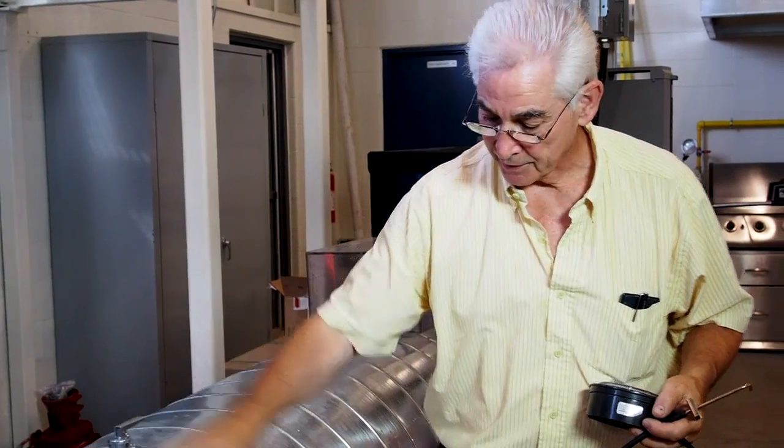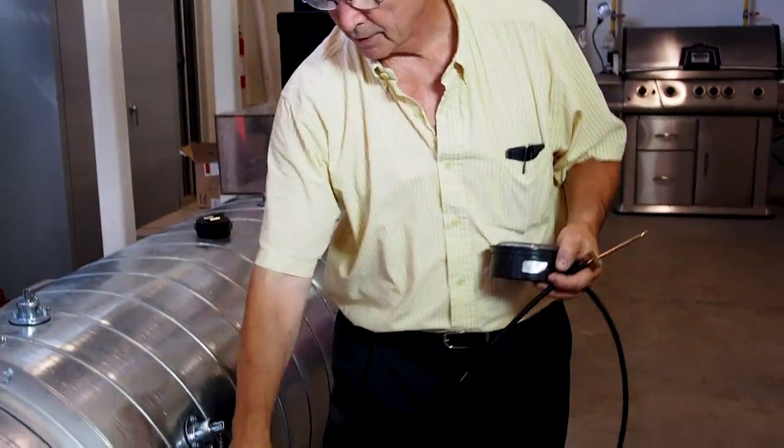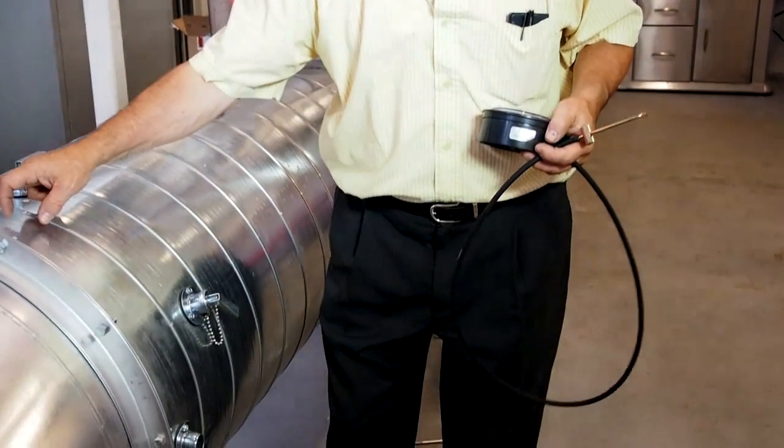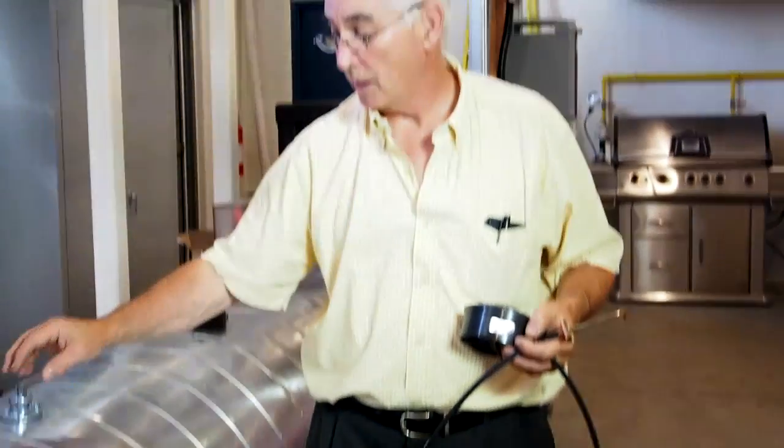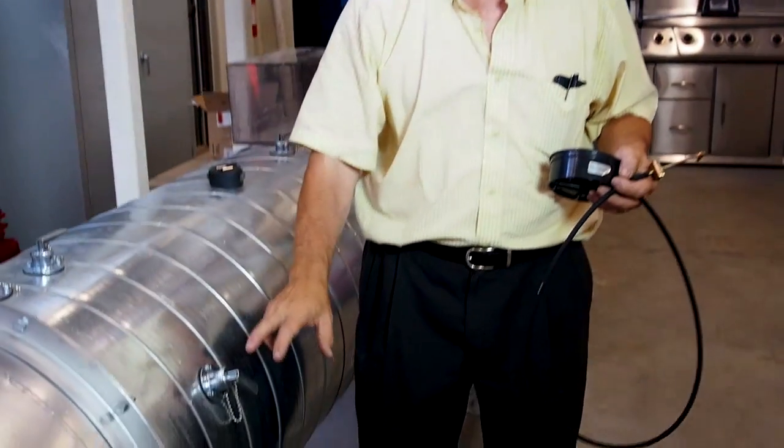On smaller ducts, we would take readings on two diameters 90 degrees apart. On larger ducts, we would take three readings 60 degrees apart.